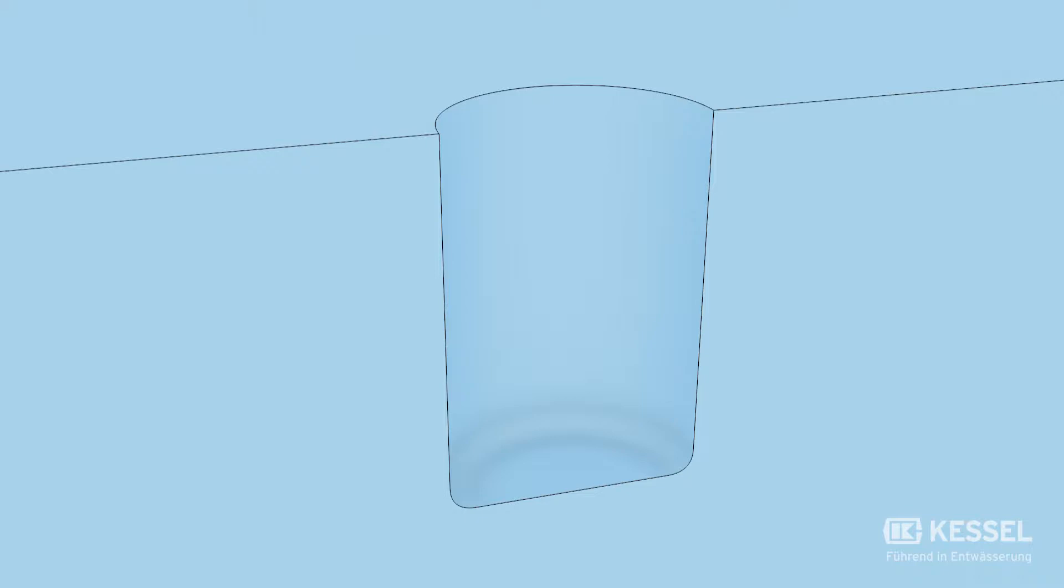Now we level the pit floor and add approximately 30cm of gravel to form a layer which we then compress to prevent any further dropping of the system. We then insert the floor element and secure its position with either lean or wet mix concrete.